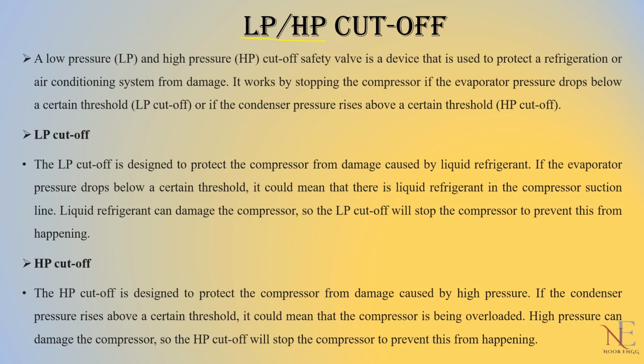So what is an LP HP cutoff? A low pressure (LP) and high pressure (HP) cutoff system is a device that is used to protect the refrigeration or air conditioning system from damage. This is the work of safety devices. This could be the first line you can say about what is an LP or HP cutoff system. It works by stopping the compressor if the evaporator pressure drops below a certain threshold, that is LP cutoff, or if the condenser pressure rises above a certain threshold, that is HP cutoff.